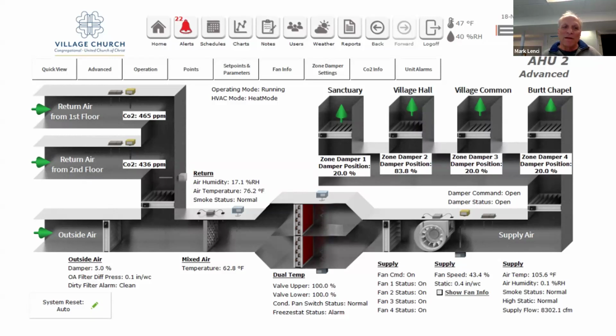So if you look from left to right, our air handling units on the roof take the return air from our first and second. This is first and second floor because this is only one of the 2 units. And then you take outside air in because you have to mix it, right? In your building, you have to keep fresh air in there. And you can see down here, right now today, at 4 o'clock this afternoon, when we took this, the combination of mixing air out of the rooms with outside air gives you air entering at 62.8 degrees to these heating coils. Now this is the dual temperature loop. So if we were cooling, instead of these being hit with hot water, they'd be cold water and they'd be cooling the air.